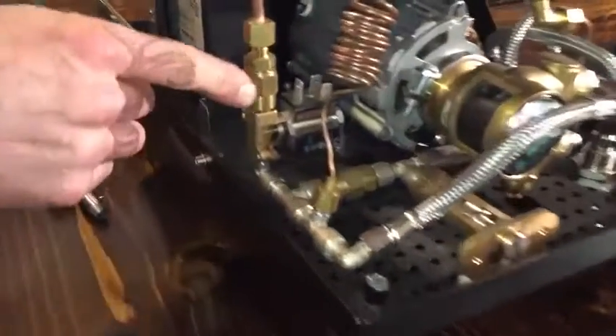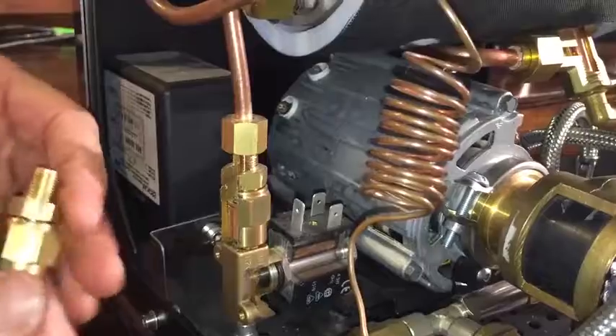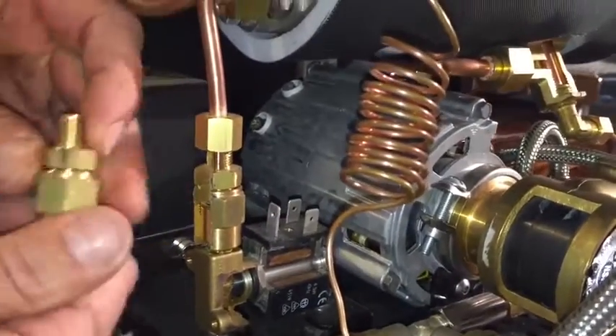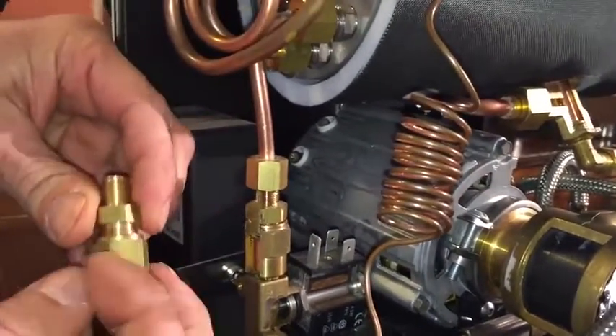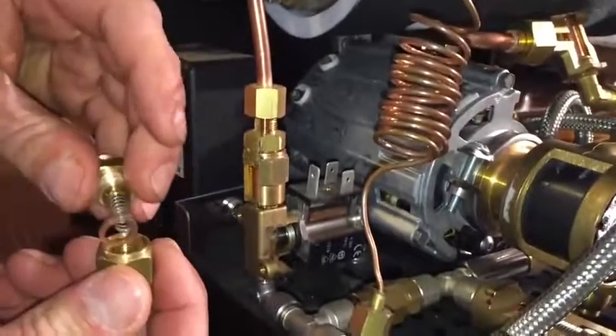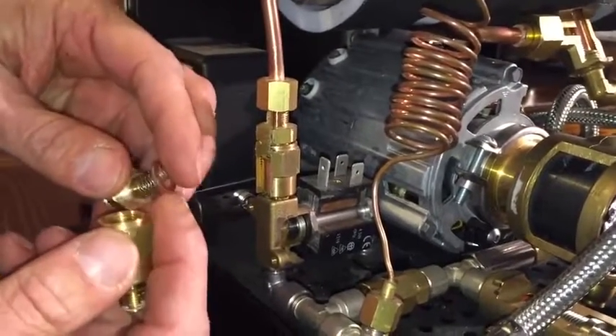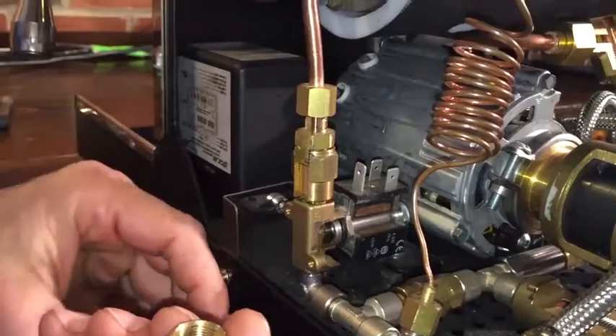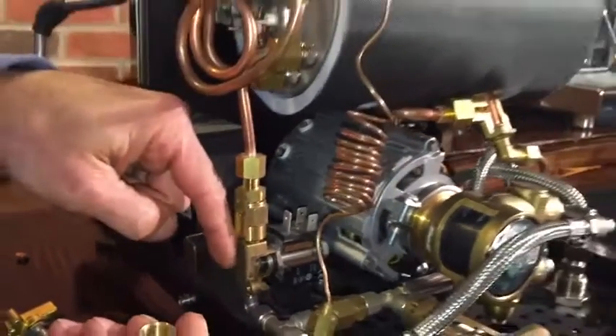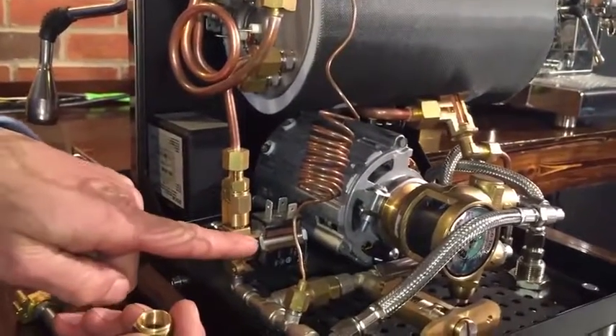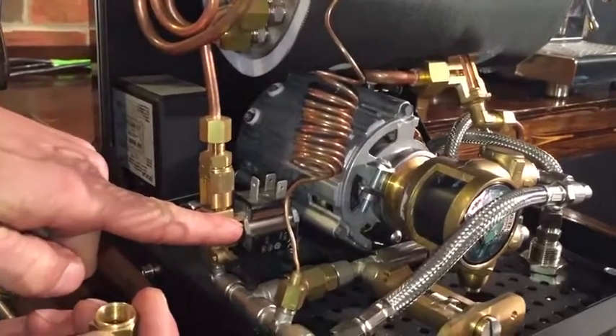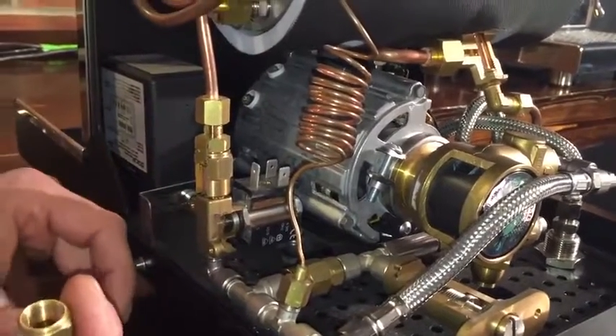So up through the solenoid valve, through a check valve - we'll spend a couple seconds on this, it's actually a really nice valve. The purpose of that is to keep water from the boiler pushing back down to the solenoid valve, going the opposite way where it could actually open that solenoid valve, remember how I showed you that pressure could open it? This will keep that from happening.